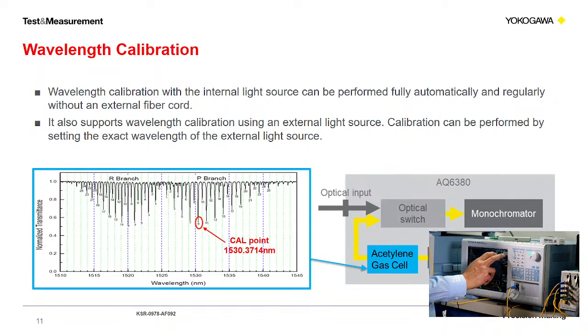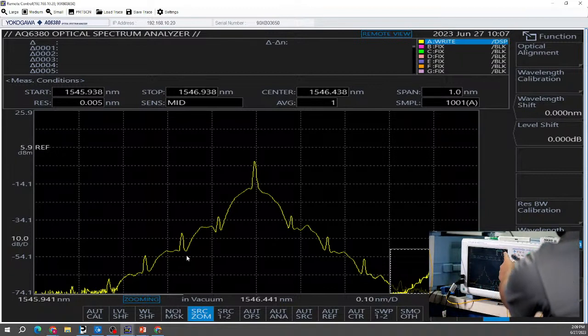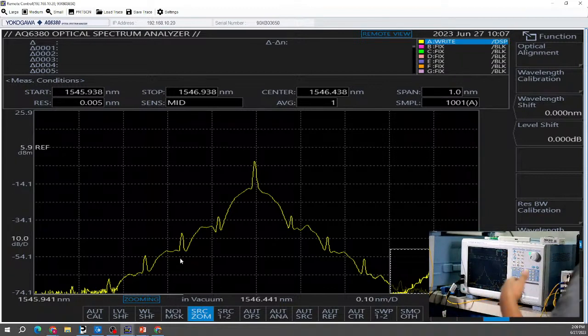And okay, I'm just going to pull up the viewer software. We're not going to execute it right now because it does take quite a little bit of time to do. We've already calibrated this unit, trust us. You would just hit that optical alignment and hit execute, and it'll do that all internally. So let me get...